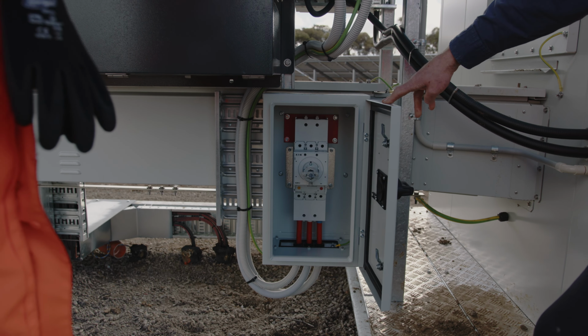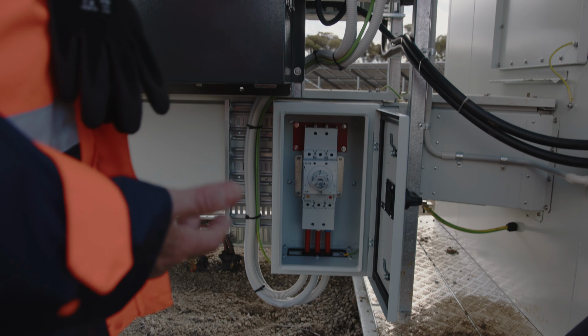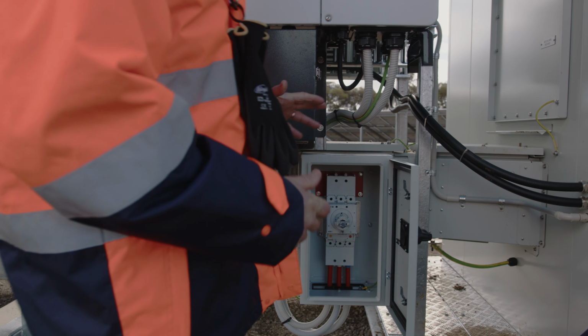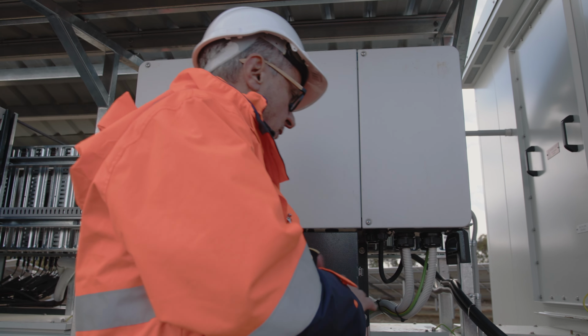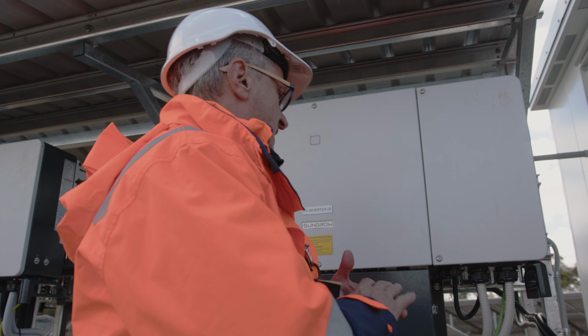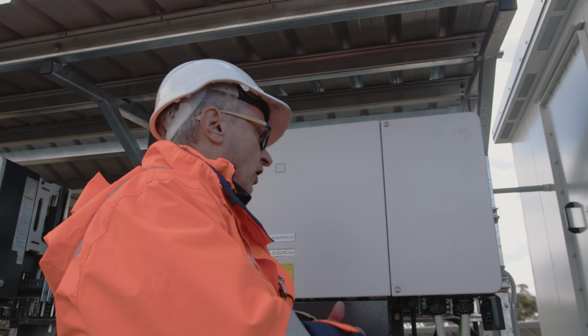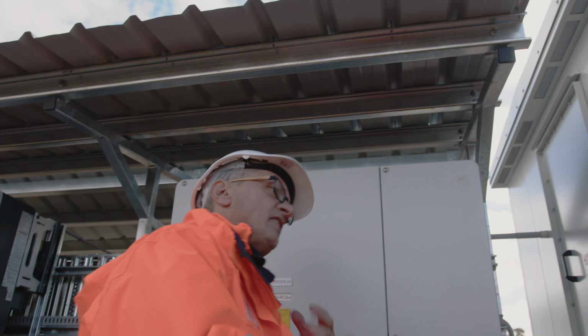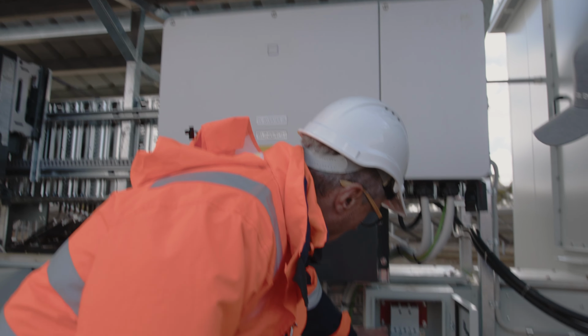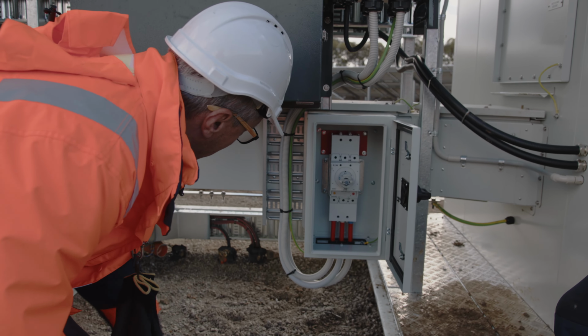I know what we tend to do on the grid safe interface protection boards is most of the time we use a 250 amp Schneider, and it's dialed down. I won't say it's derated, because it's not, it's actually physically dialed down. This breaker here looks like it's an Eaton.